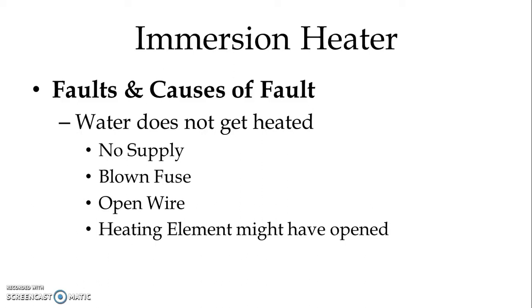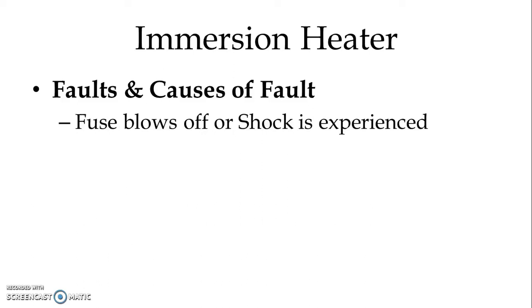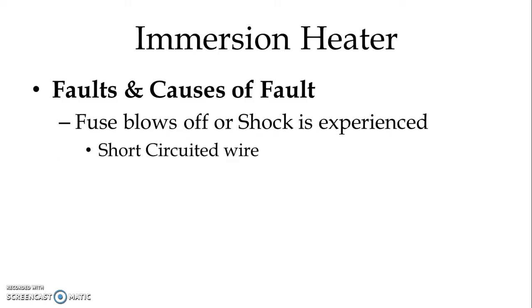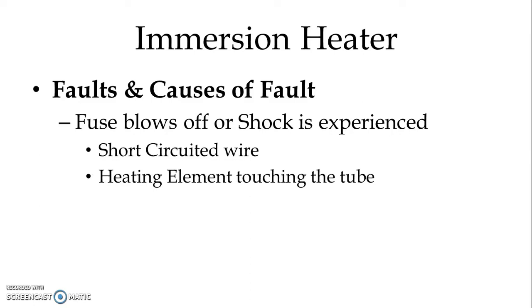The second fault is that the fuse blows off. When we start the heater, the fuse blows, or sometimes we experience a shock. There must be a short circuit somewhere in the wire, or the heating element might be touching the tube and creating an earth-type fault.